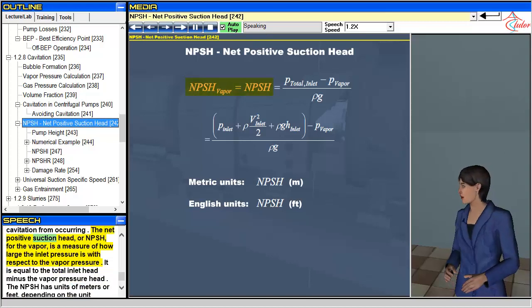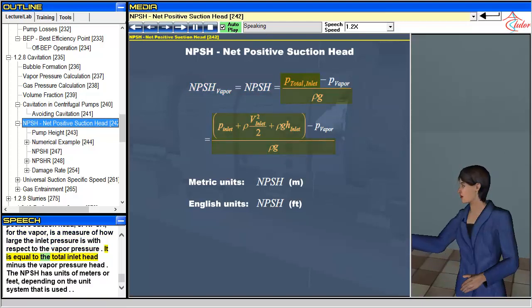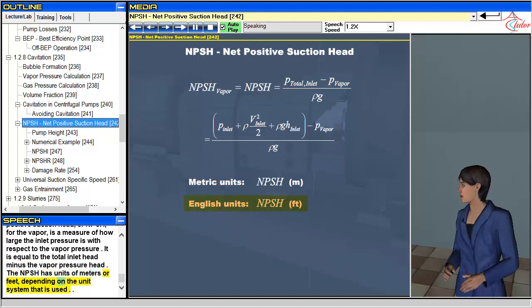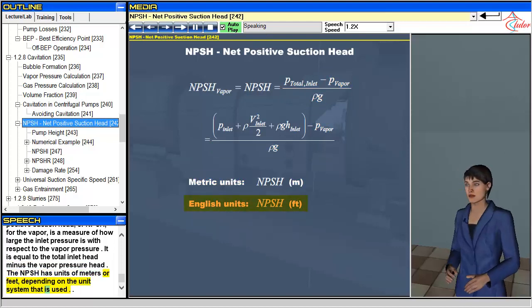The net positive suction head, or NPSH, for the vapor is a measure of how large the inlet pressure is with respect to the vapor pressure. It is equal to the total inlet head minus the vapor pressure head. The NPSH has units of meters or feet, depending on the unit system that is used.